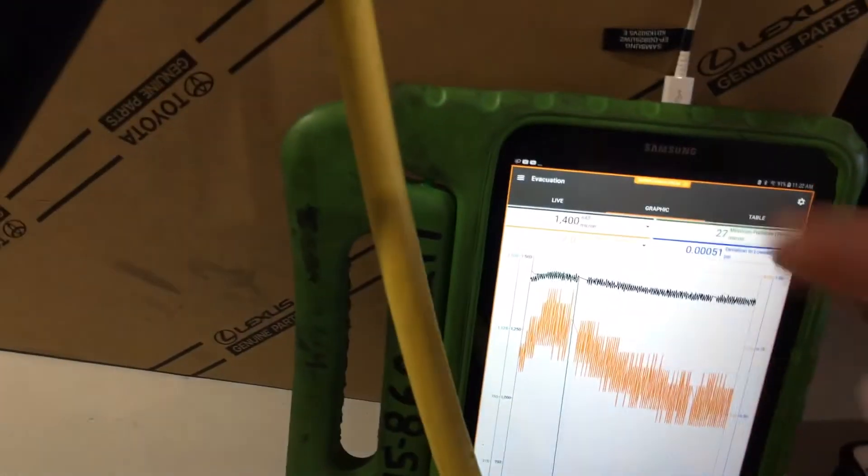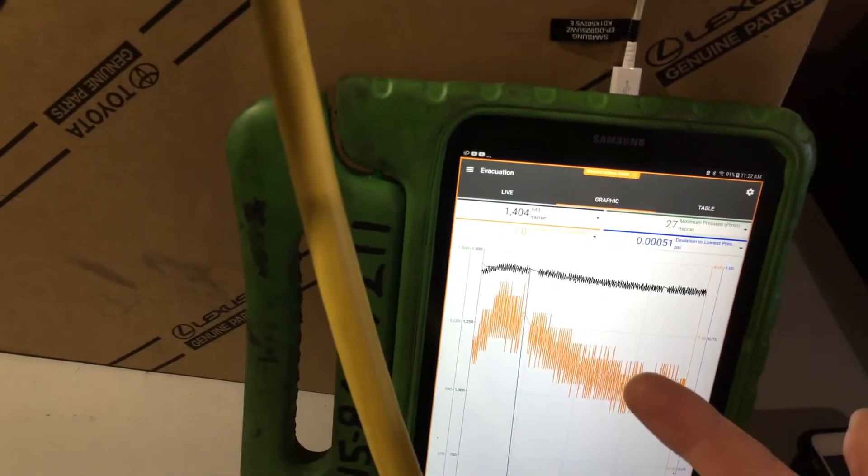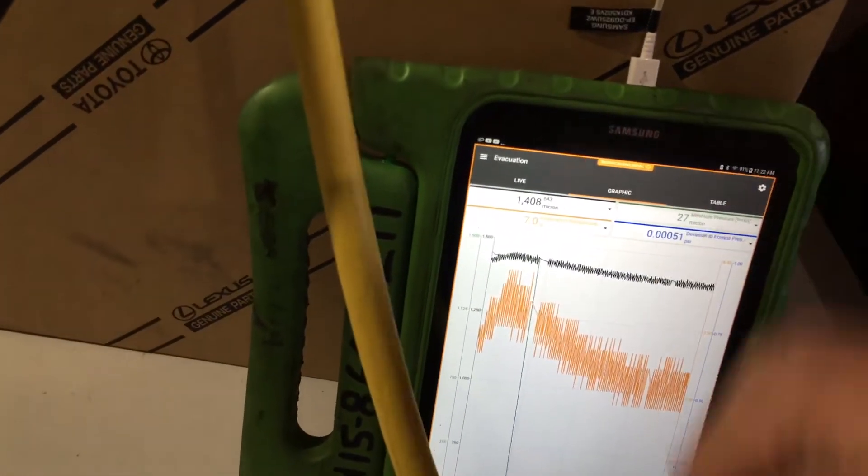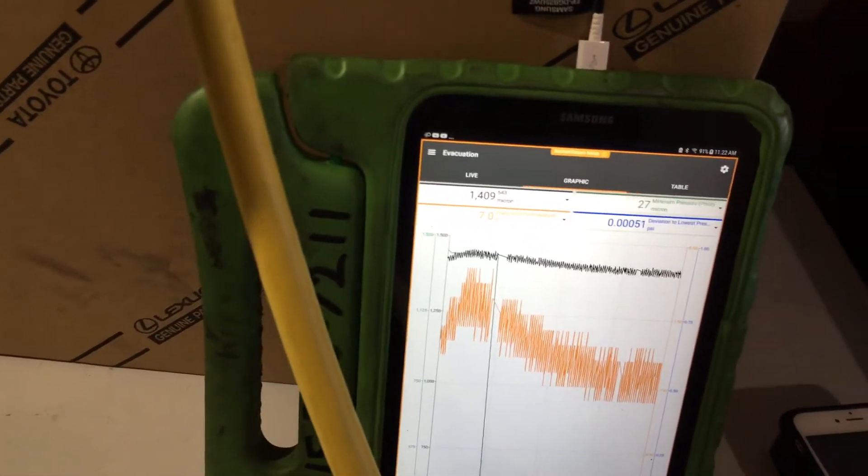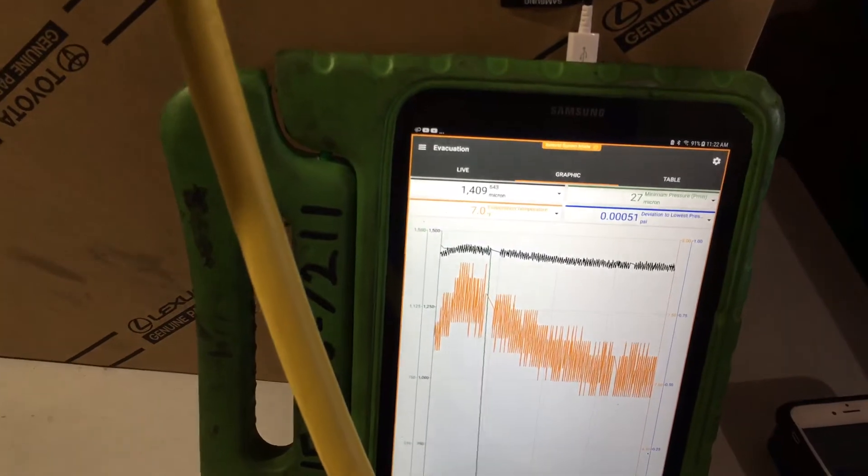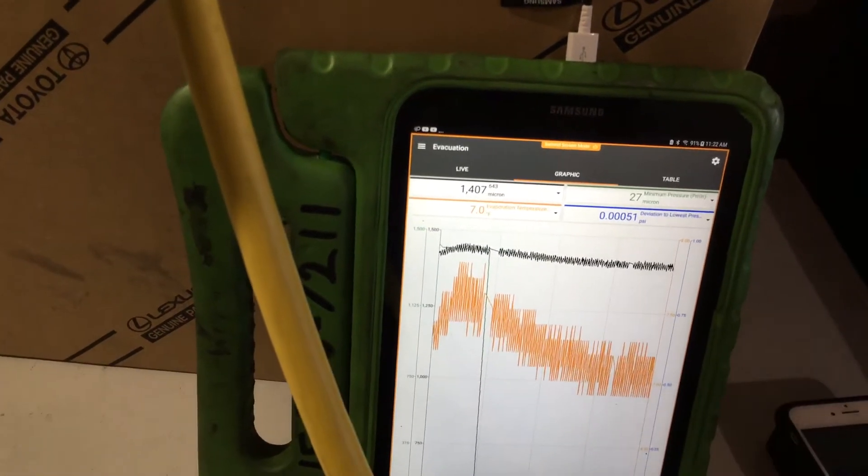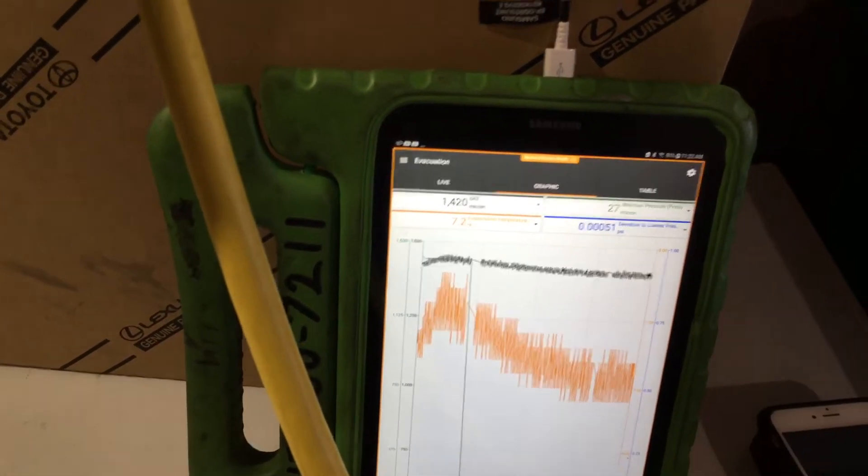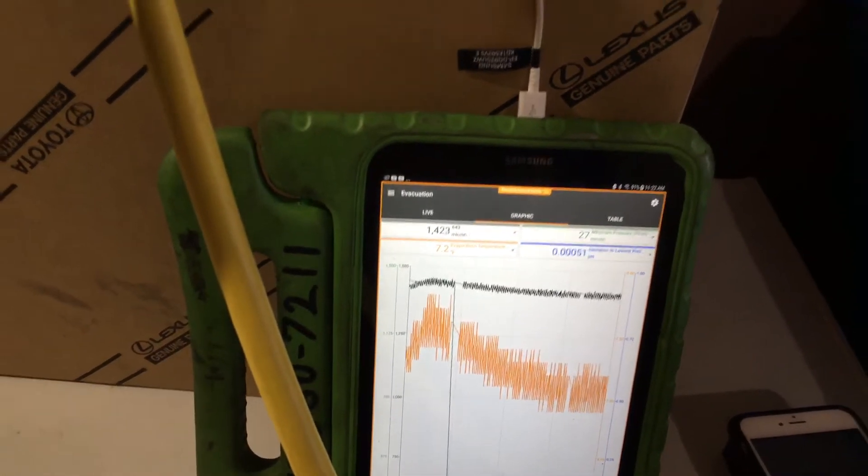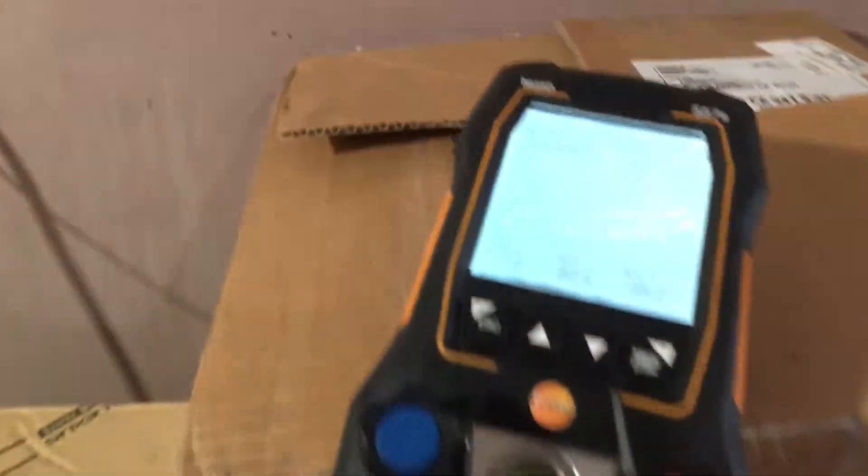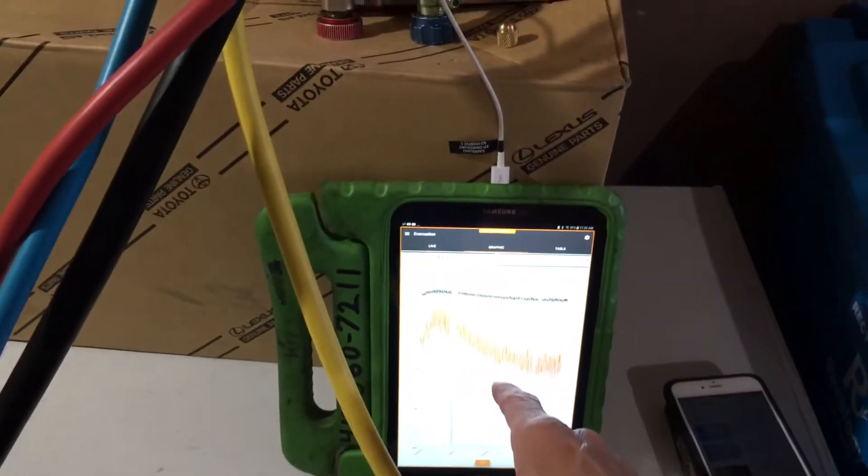It was losing vacuum. I put it back on the vacuum pump, got it down to 27 microns, and then closed off the vacuum and let it decay to this morning. The only problem is the software stopped connection with the Micron and I lost all my data.